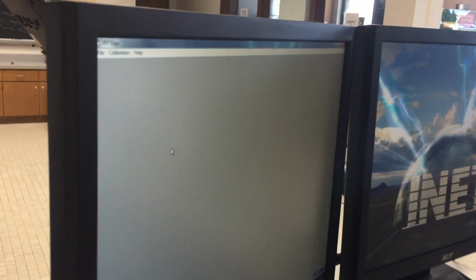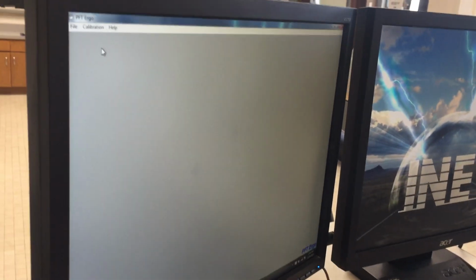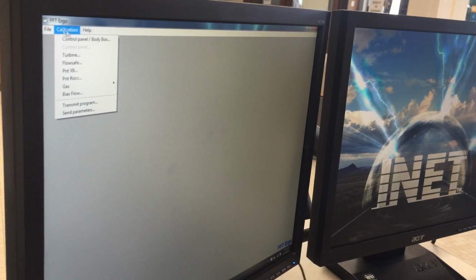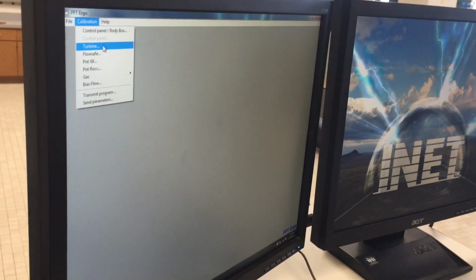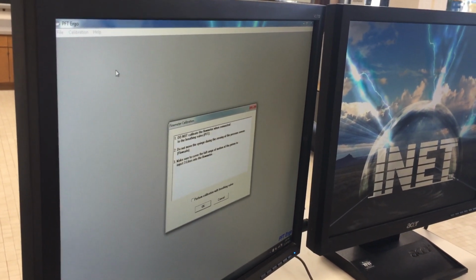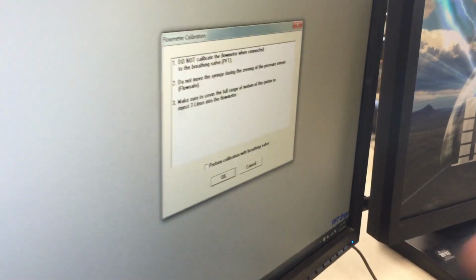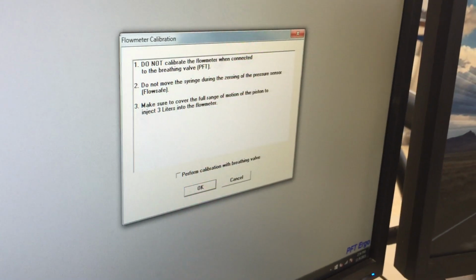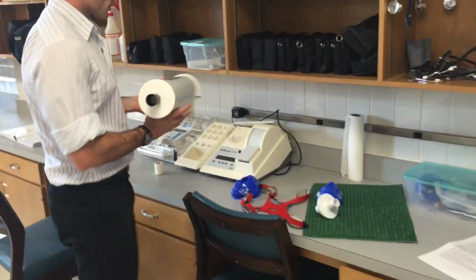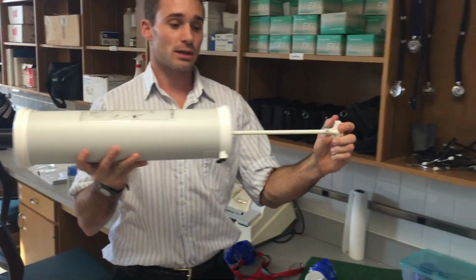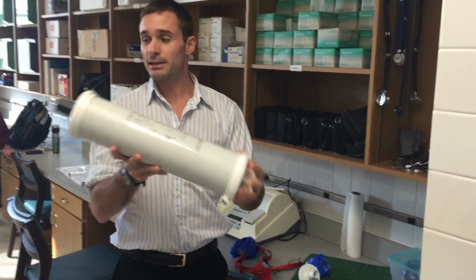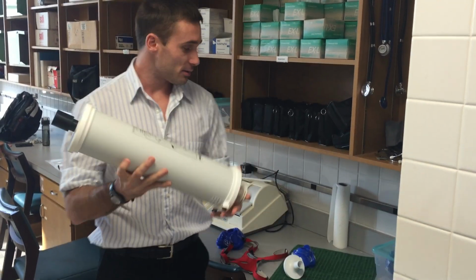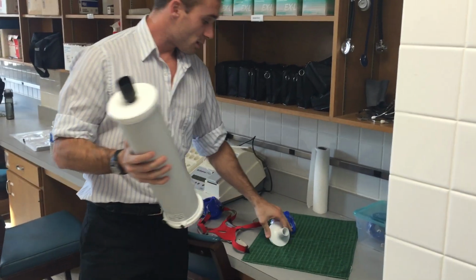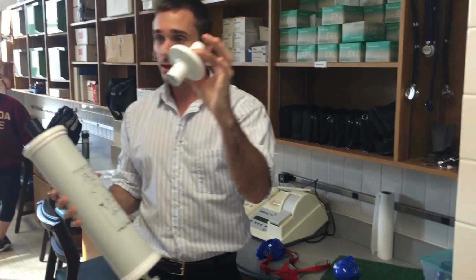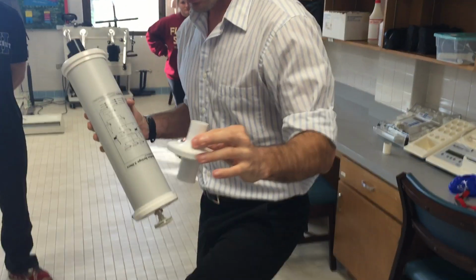So we've done the electronic portion of the calibration, now we need to do the manual portion. Calibration, and now this time we're going to turbine. We click turbine, this screen pops up, but before we do anything else, we move over to this side of the lab and we find our 3-liter syringe, just like this. Not the kind that you get a needle with, but to calibrate the machine. We need to get our connector tube right here, and then we'll grab our flow meter.